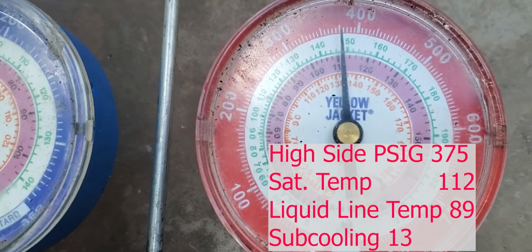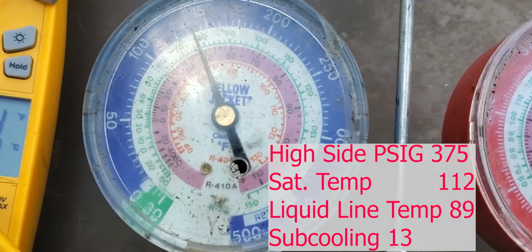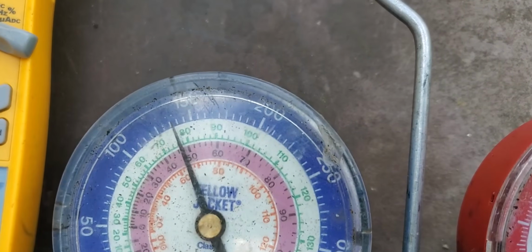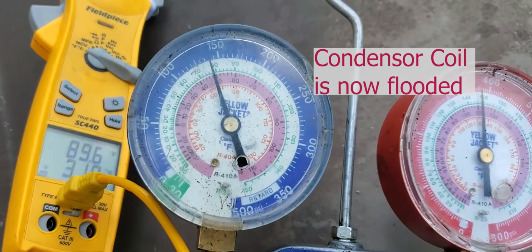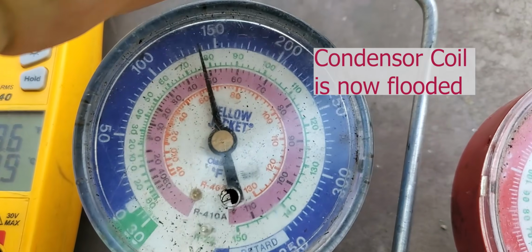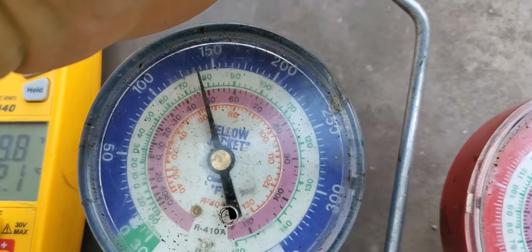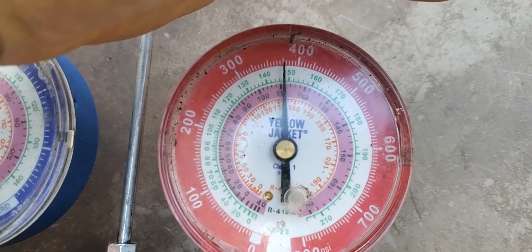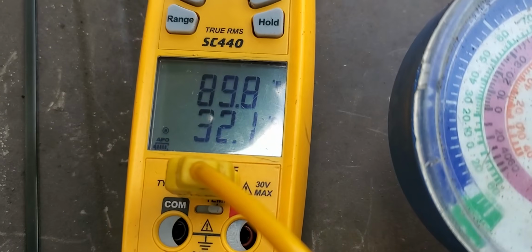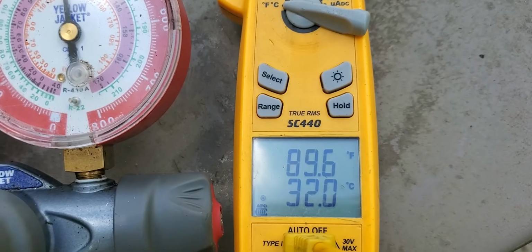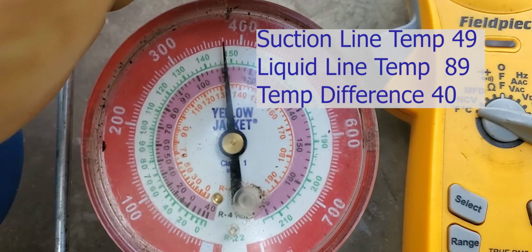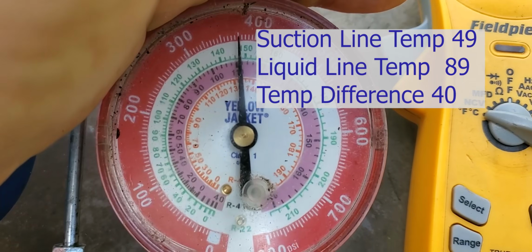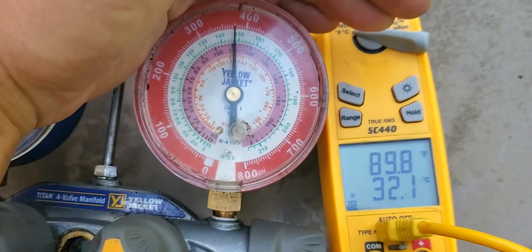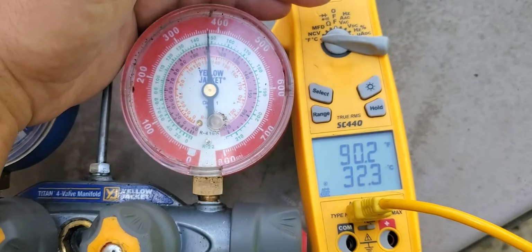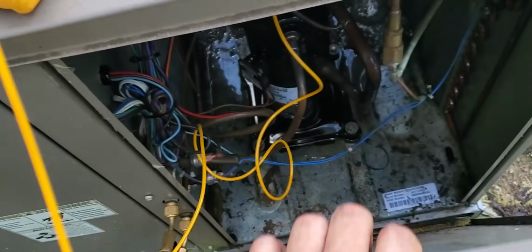And you're going to notice in the field with air conditioning systems using 410A that the 40-degree temperature difference we have between the suction line and the liquid line is going to be relative. You're going to begin to check these values and monitor more and more and realize that when the suction line temperature starts to drop, you're going to be able to know when your unit has enough refrigerant. If you want to take more time to look at the measurements I put on the screen, pause the video throughout and look at those measurements.